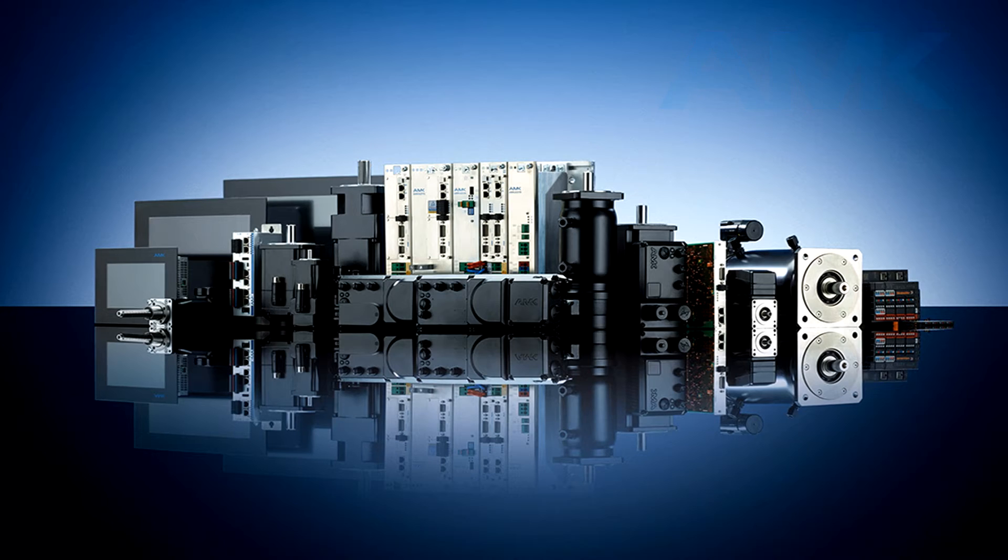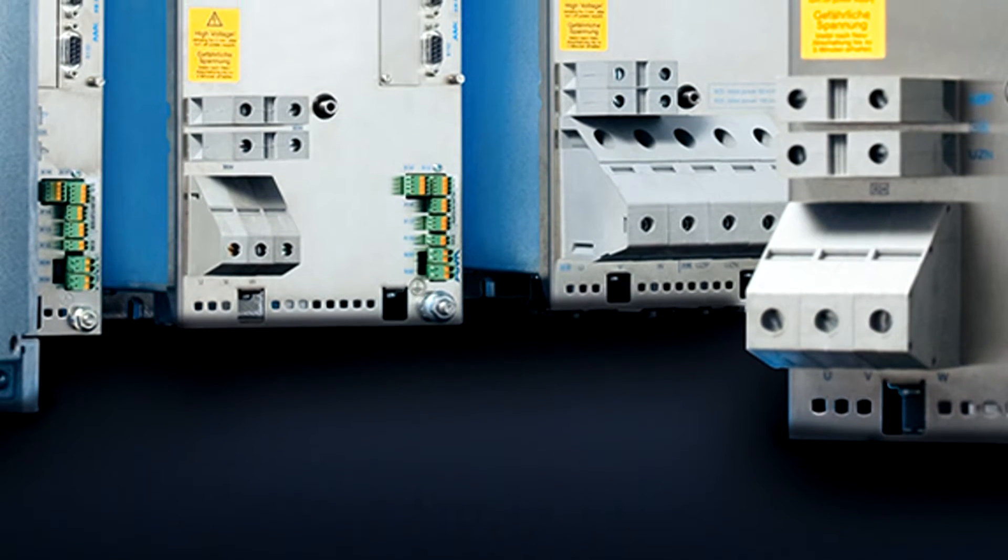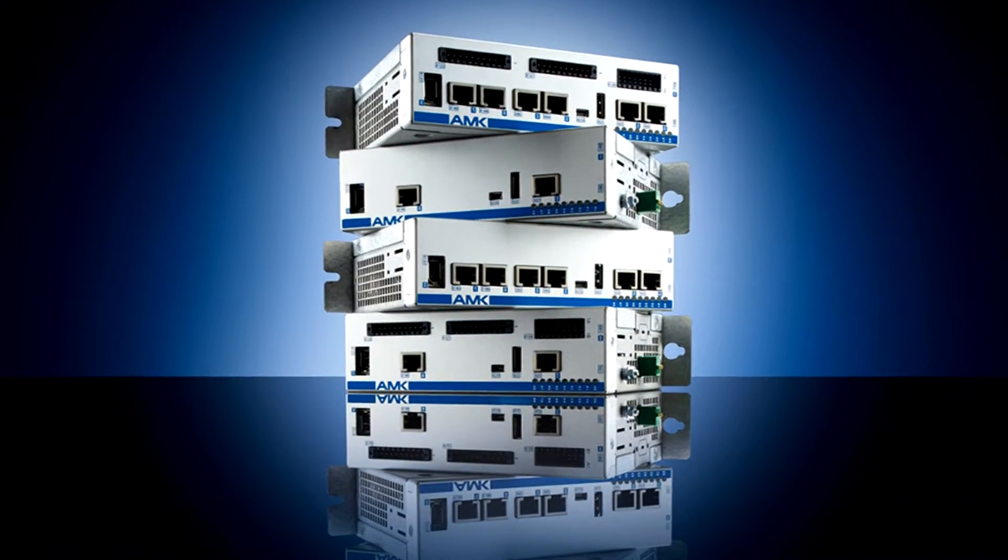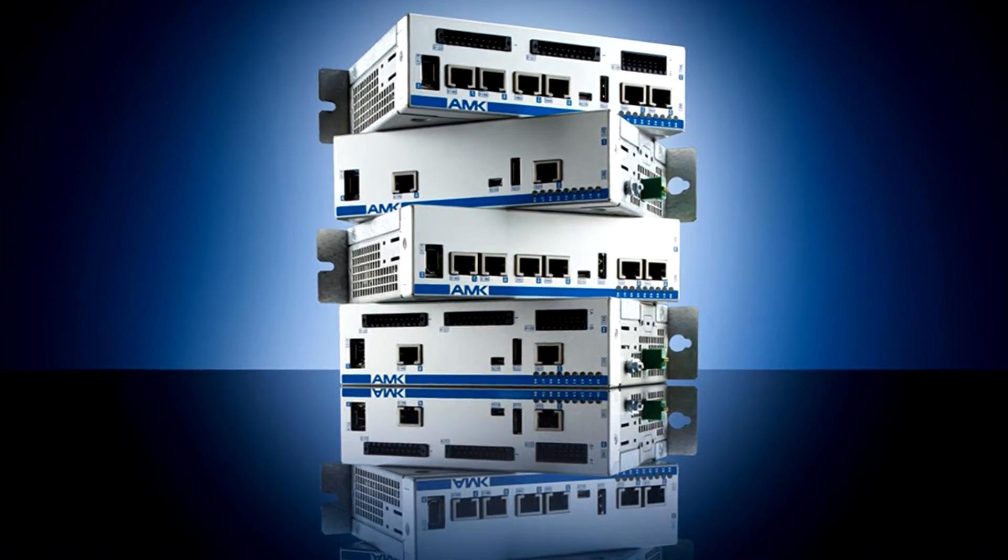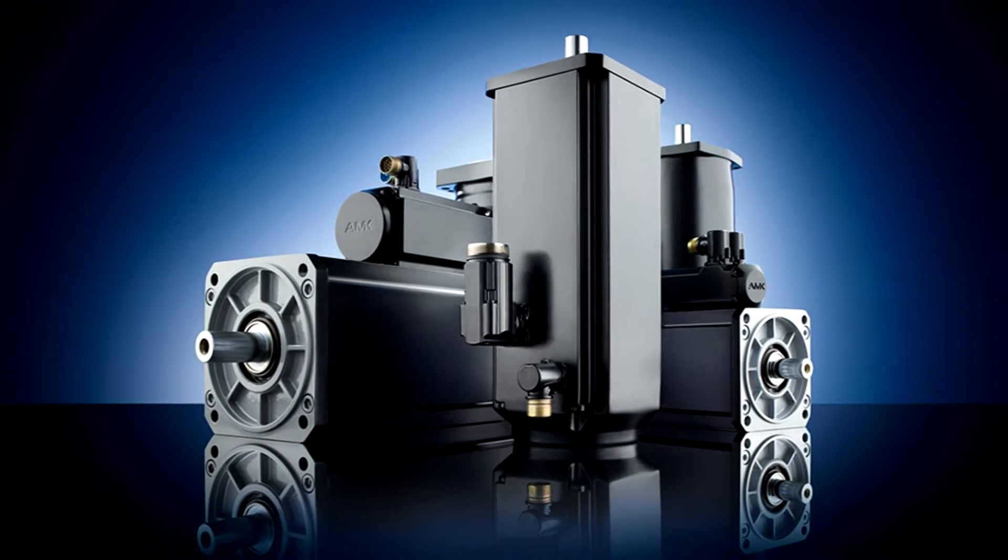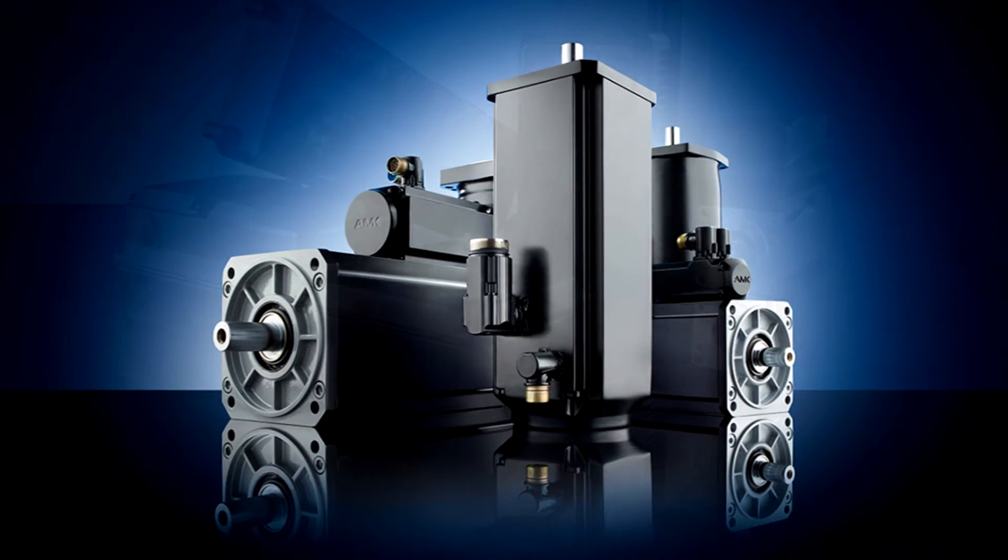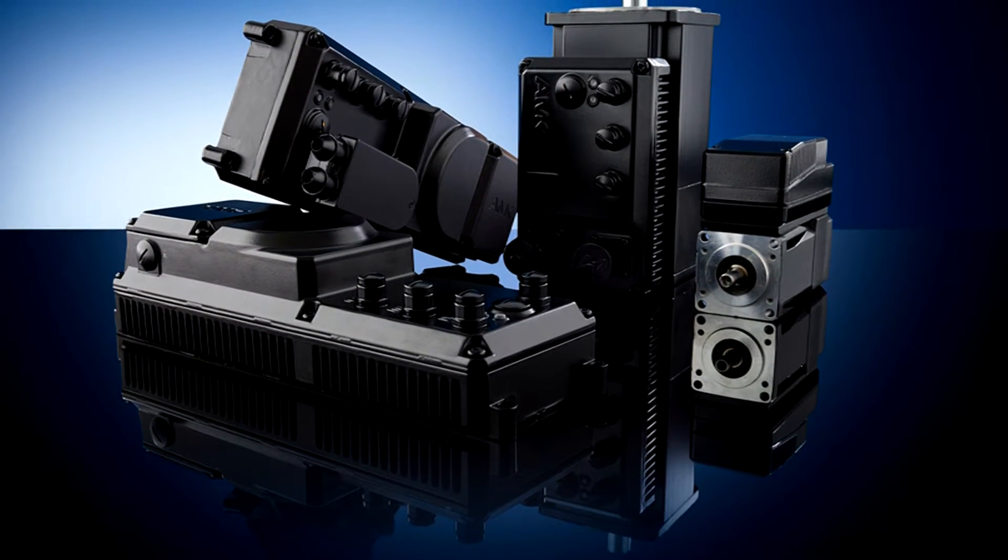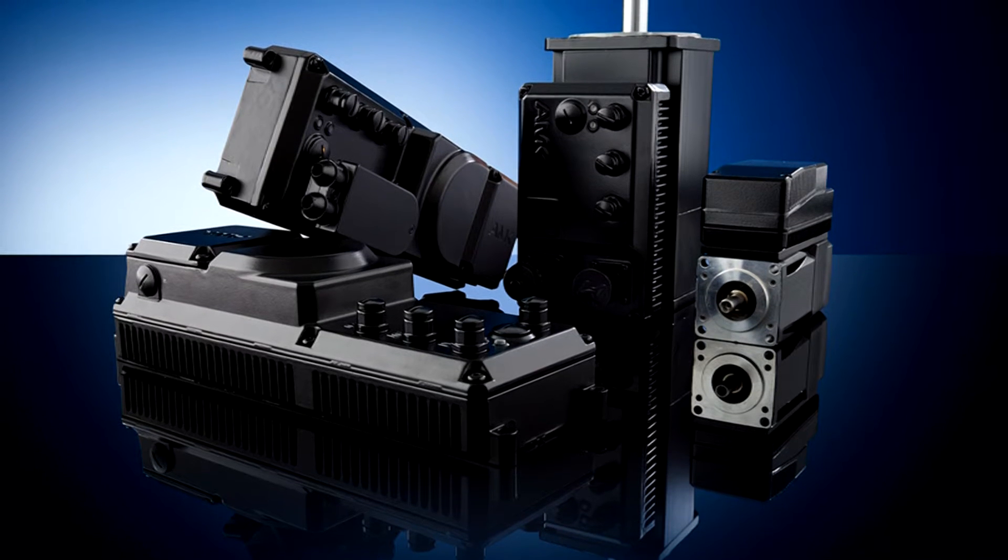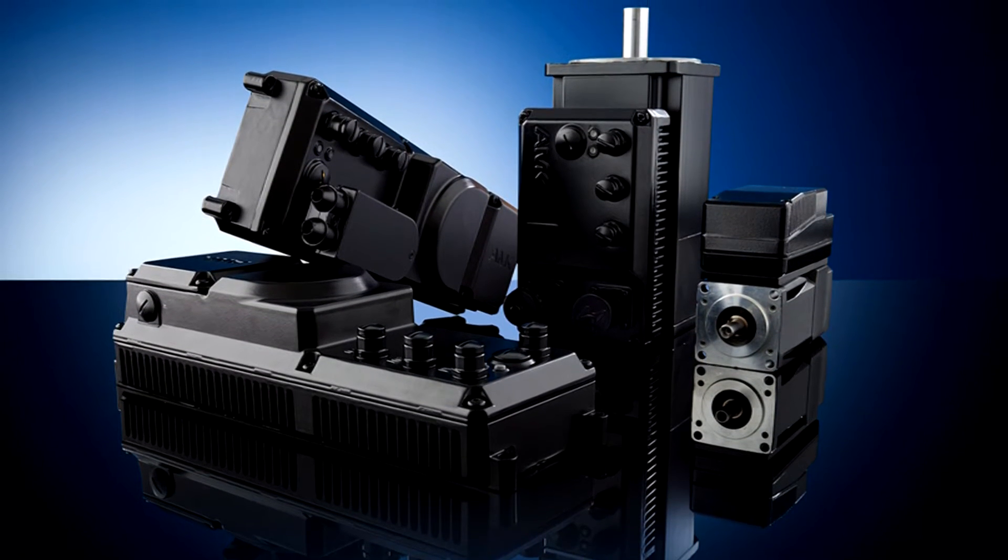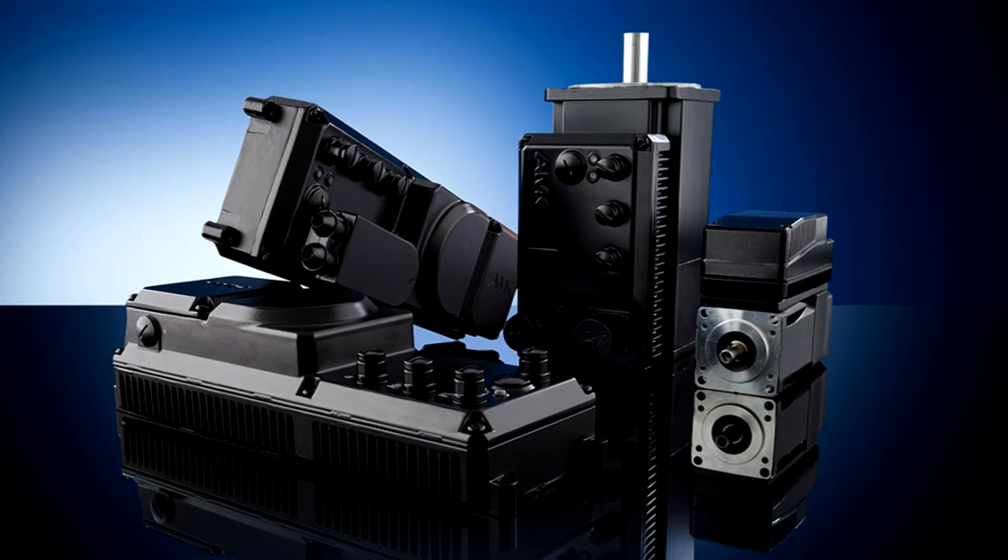We manufacture both centralized and decentralized servosystems. Centralized traditional systems are designed to be mounted in an electrical cabinet, and the power and feedback cables for the motor are routed from the units in the cabinet to the motors. Decentralized systems are designed to be mounted on the machine, either on the motor or in very close proximity to it. These units reduce cabling and electrical panel requirements.